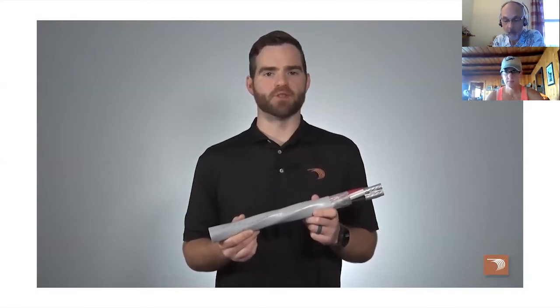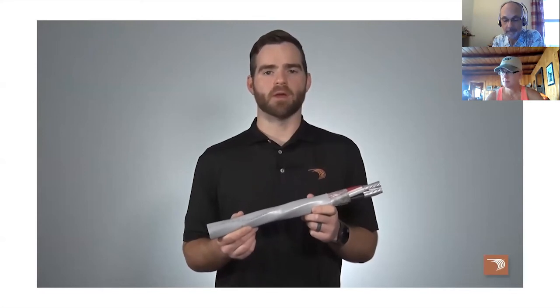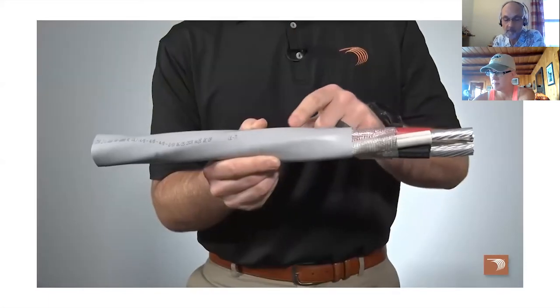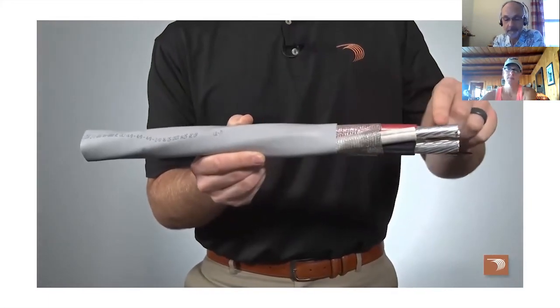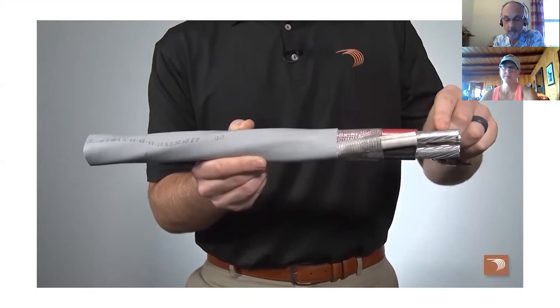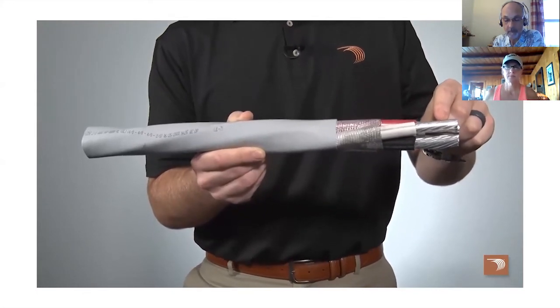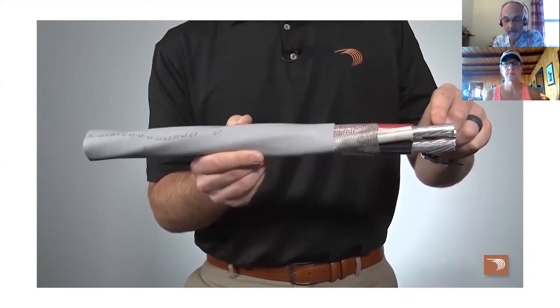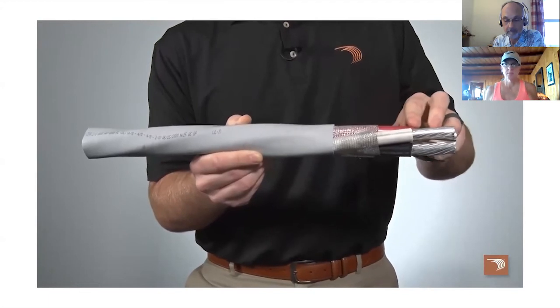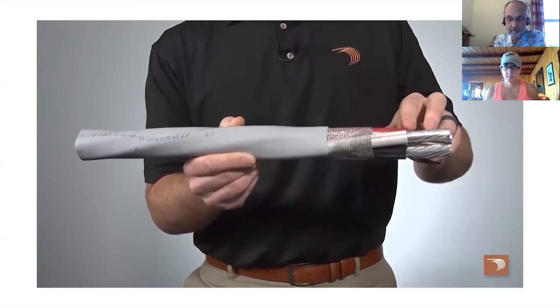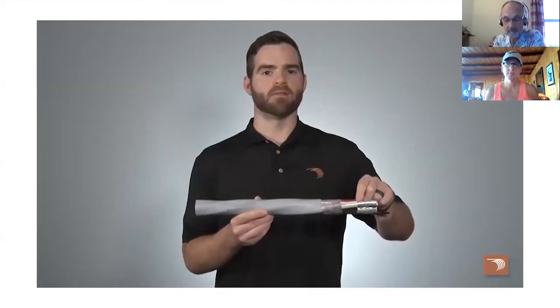Our tray cable SER hybrid cable utilizes a more robust jacket or sheathing than normal SER cable, making it less prone to damage during tough residential and commercial installation. It's constructed with a PVC outer jacket with stranded aluminum or copper THHN/THWN-2 or XHHW-2 inner conductors. The inner conductors are flame retardant, sunlight resistant, and come in black or colored polyvinyl chloride, or PVC.